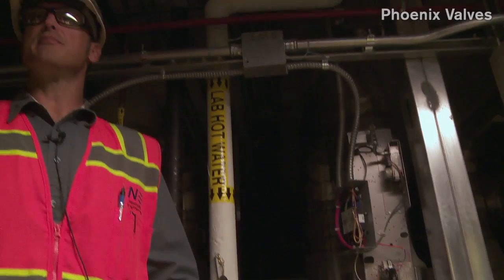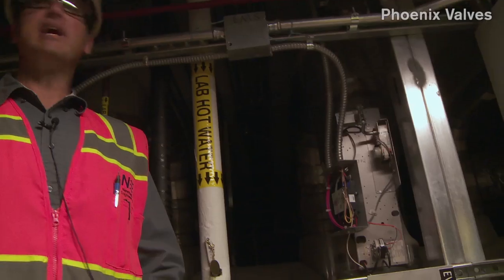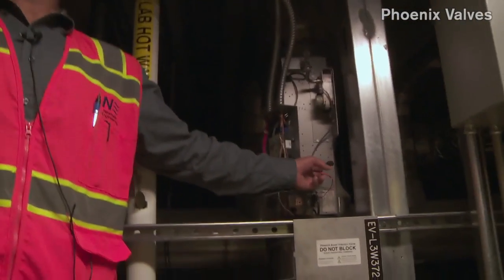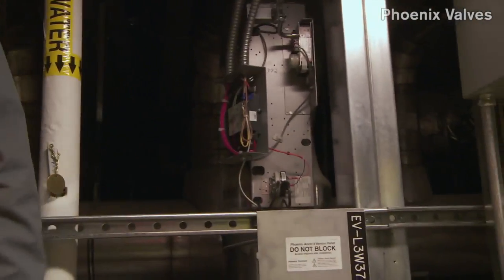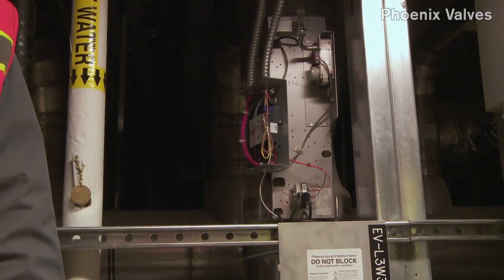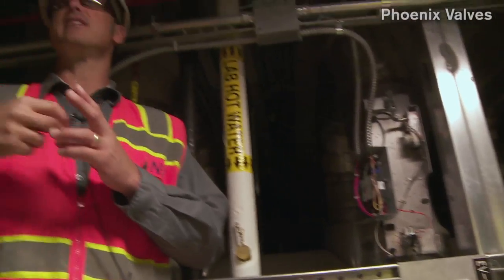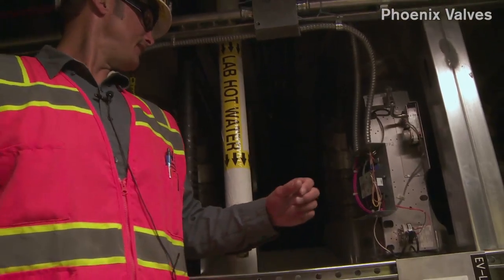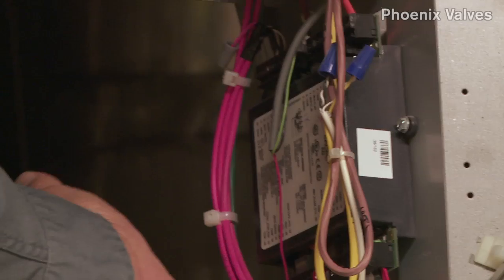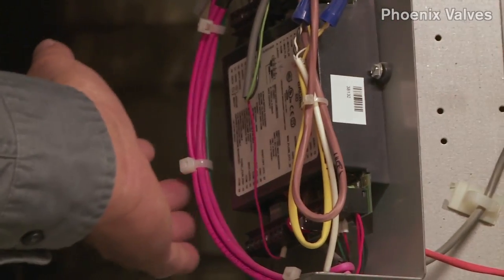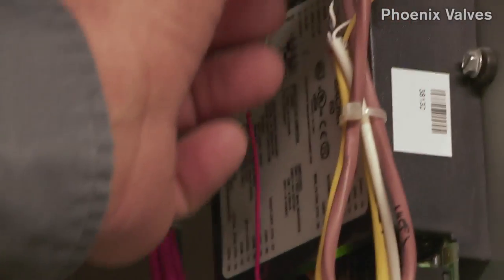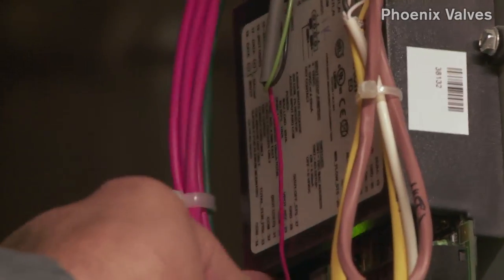You would actually see it at the fume hood monitor. And then we have a Johnson Controls 2-conductor. There's an actual alarm, a normally open or normally closed contact alarm, in the fume hood monitor that we're able to send that same signal to the front end. You basically just have your regular comm. It's MSTP comm. I believe there's a switch.